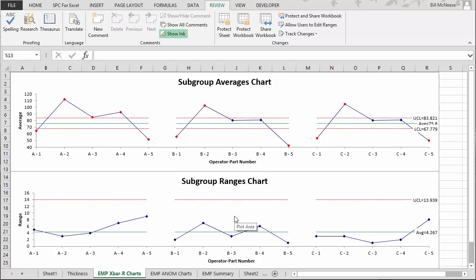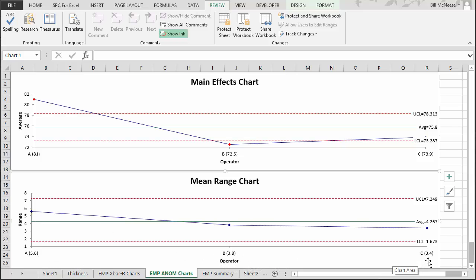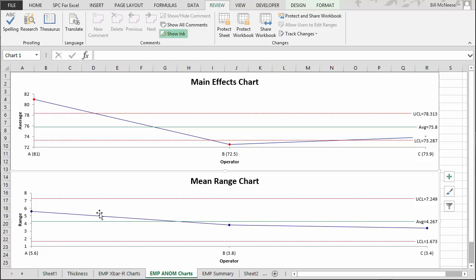You can confirm your conclusions about the ranges being the same by constructing a mean range chart. You calculate the average range for each operator: Operator A had an average range of 5.6, Operator B 3.8, and Operator C 3.4. You plot those, calculate an overall average, and add control limits — not classical control limits, but scaling-factor-based limits that serve the same purpose. All three ranges are within the control limits, implying that each operator has the same repeatability or test-retest error.